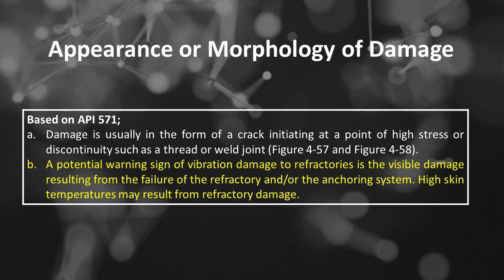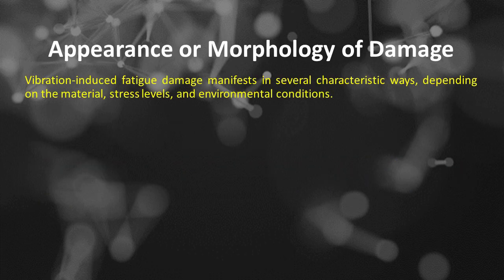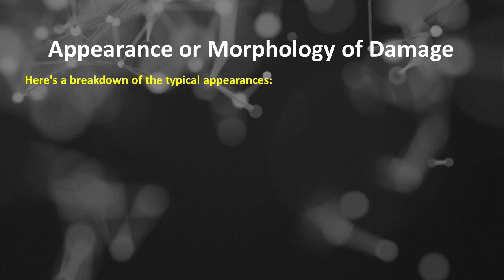The second is a potential warning sign of vibration damage to refractories is the visible damage resulting from the failure of the refractory and/or the anchoring system. High skin temperatures may result from refractory damage. Vibration-induced fatigue damage manifests in several characteristic ways, depending on the material, stress levels, and environmental conditions. Here's a breakdown of the typical appearances.